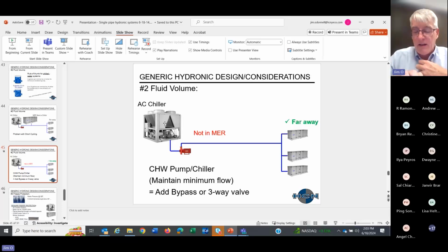That turns into a velocity of, just pick a number, 10 feet per minute through the chiller. With a variable pumping system, as your load reduces, they'll reduce the water flow and try to keep the same delta T across the chiller. But through your bundles, through your heat exchanger, as the flow reduces, your velocity reduces. Eventually the velocity gets too low and creates laminar flow at the heat exchanger, and then you end up getting improper heat transfer.